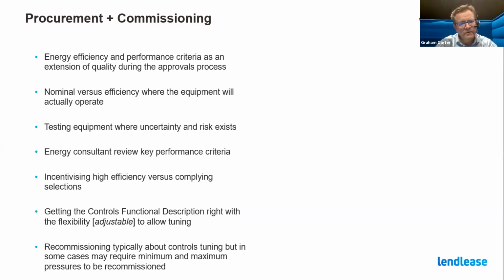Test equipment where there's uncertainty and risk, ranging from active chill beam turn down testing to chiller testing, and involve the energy consultant to review key performance criteria. The mechanical consultant should take the lead, but share what they're seeing from an efficiency point of view with the energy consultant, who should be given an opportunity to tick off on that as well.